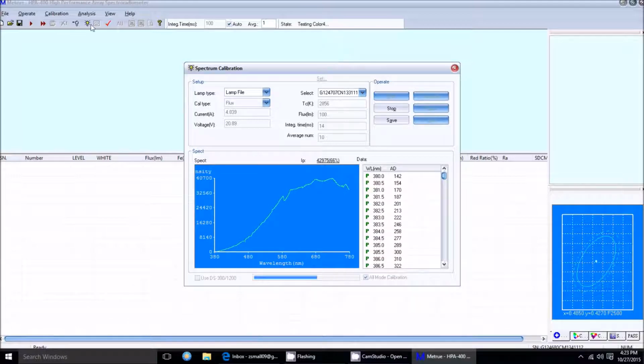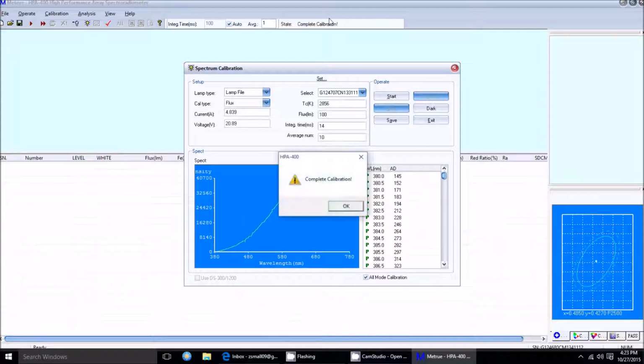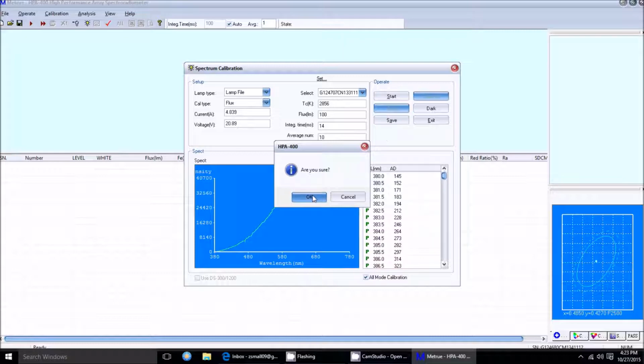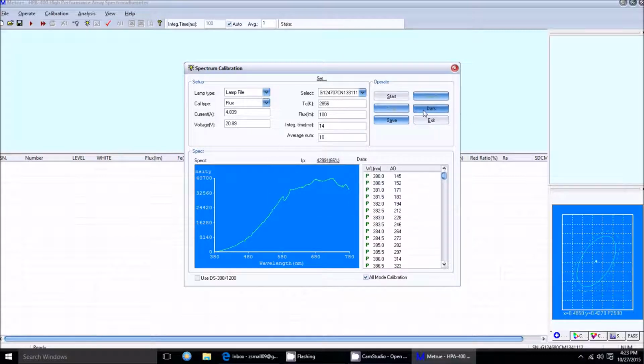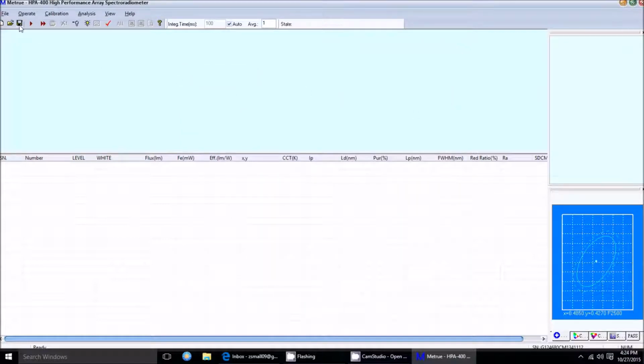And then while it's running, you can see up here what it's doing on the state. It will tell you. So the color refers to the color filter that it's currently using in this spectroradiometer. Those are used for precise mode. In fast mode, there is no filter. Okay, calibration complete. Hit OK. Make sure you save your file before you exit. Are you sure? Yes. Save. Okay, I can now exit, and I can now take a measurement.